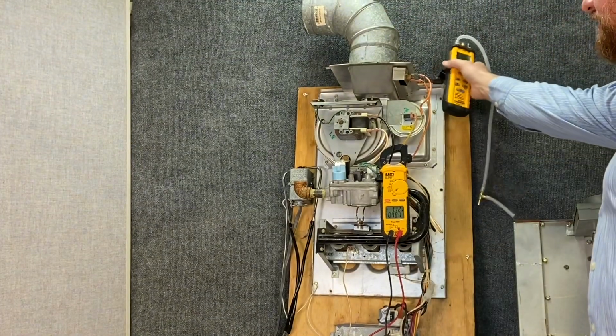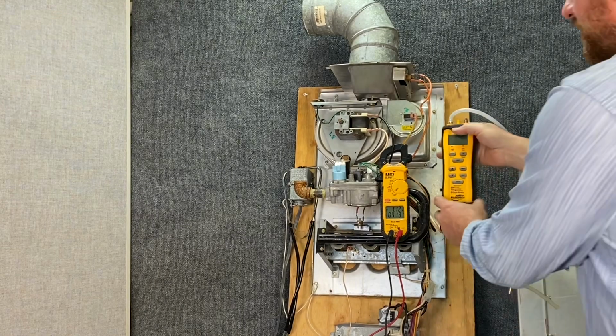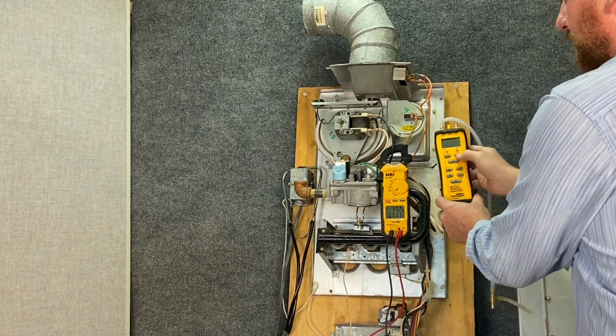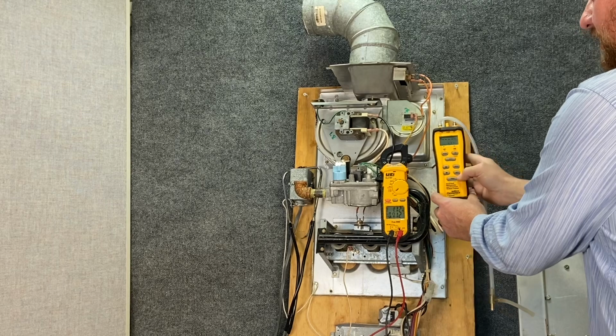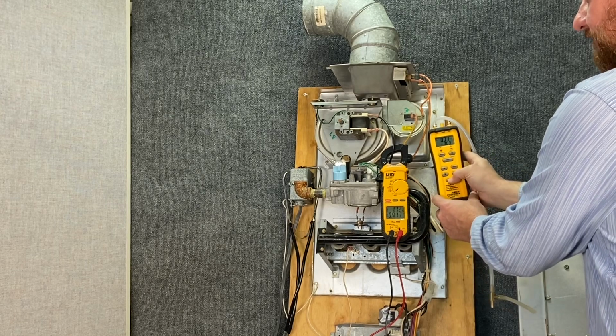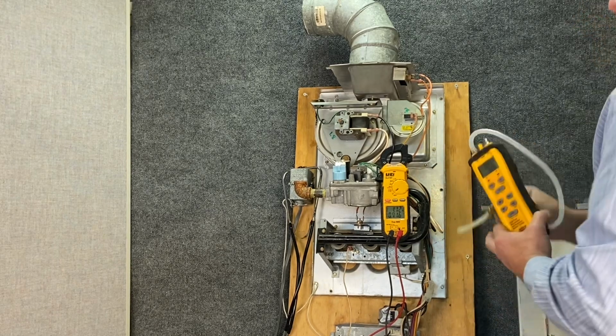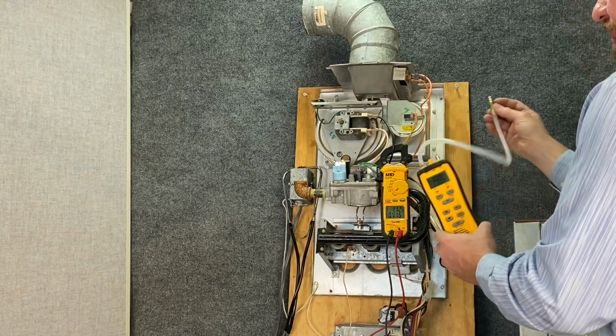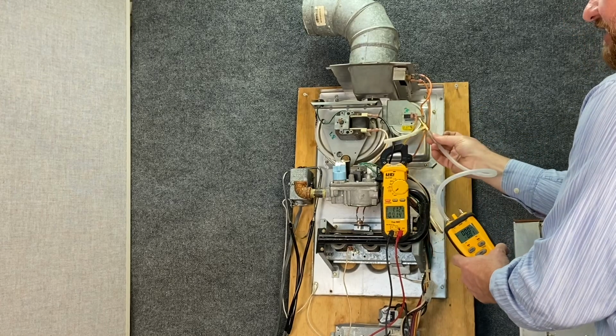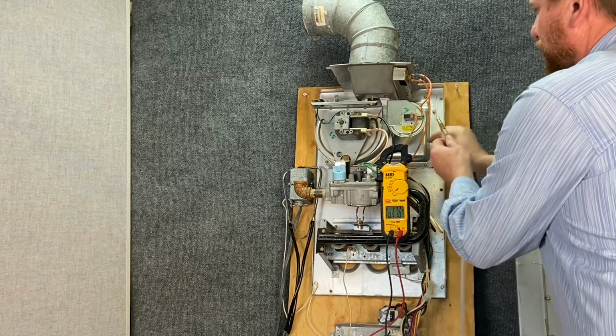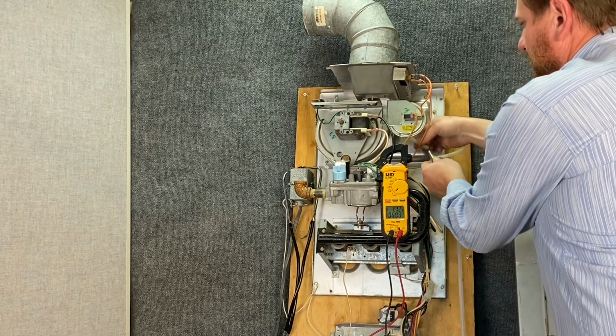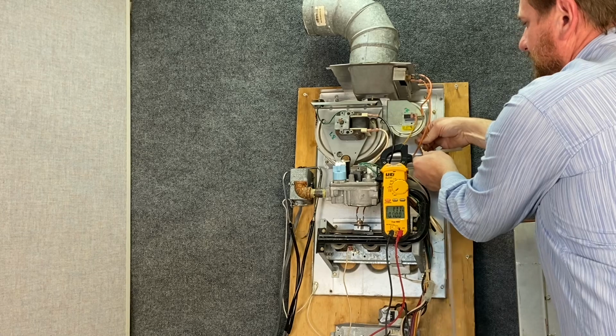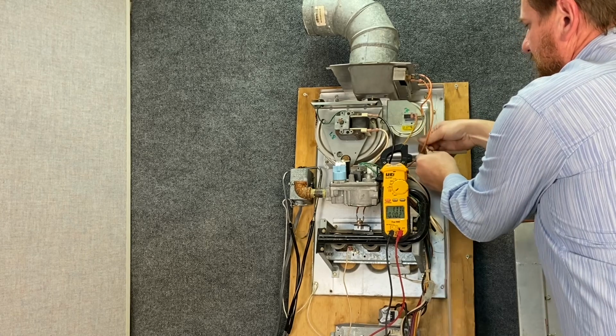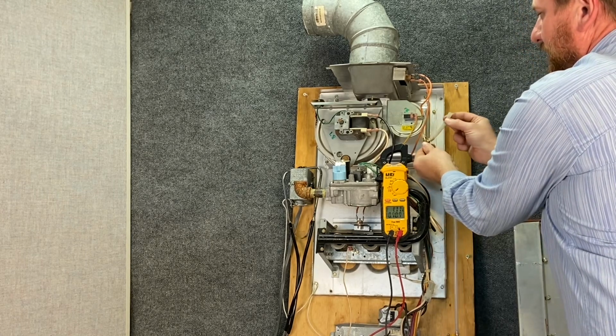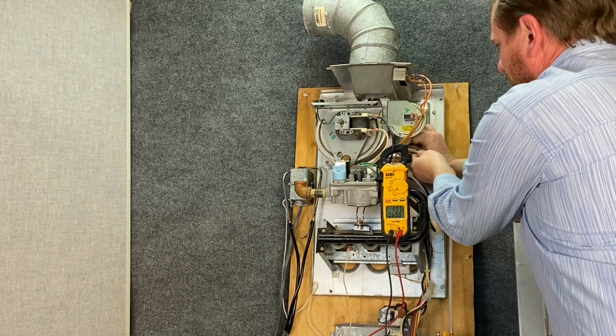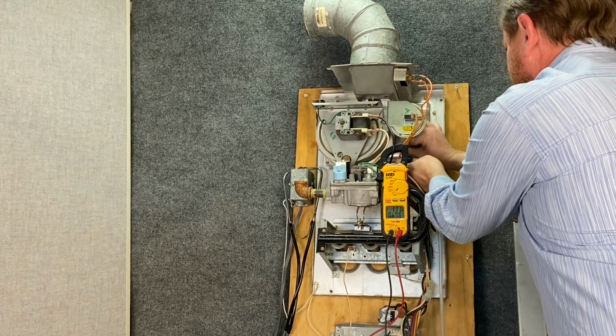What we have here is a digital manometer. This is what we're going to use to check the pressure. So I'm going to turn this on, and the next thing I do is zero it out. To check pressure, we're pulling a vacuum, so this is going to be negative pressure. I have this nice little T, and I'm going to take the loose hose that we have and connect it on my T. The existing tubing I have, we're going to put onto the collector box.